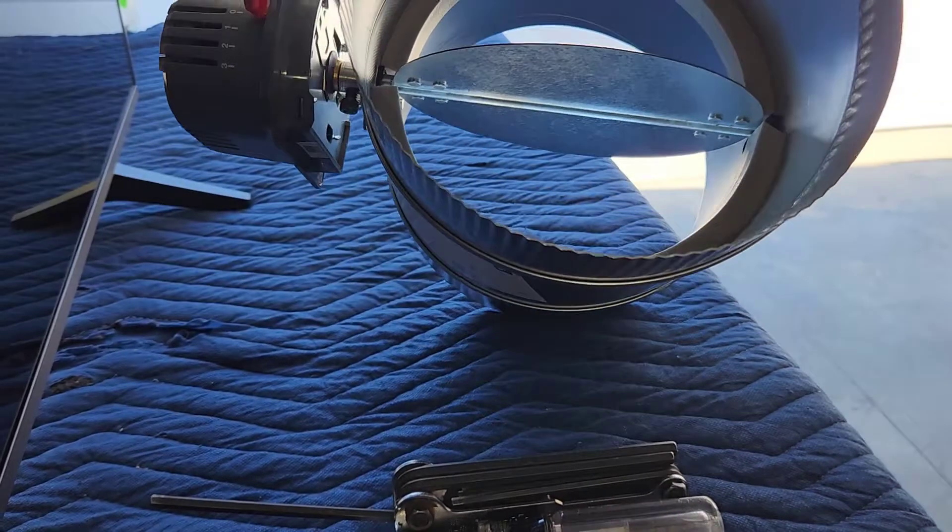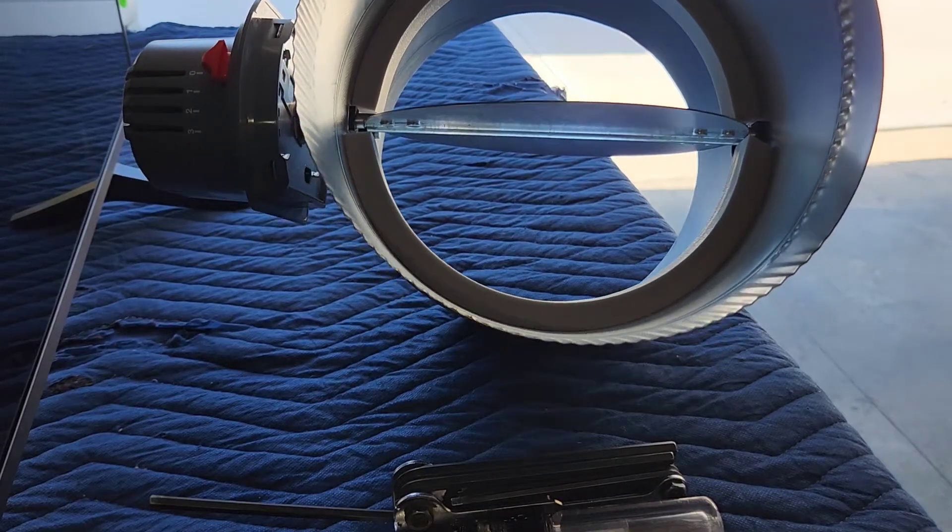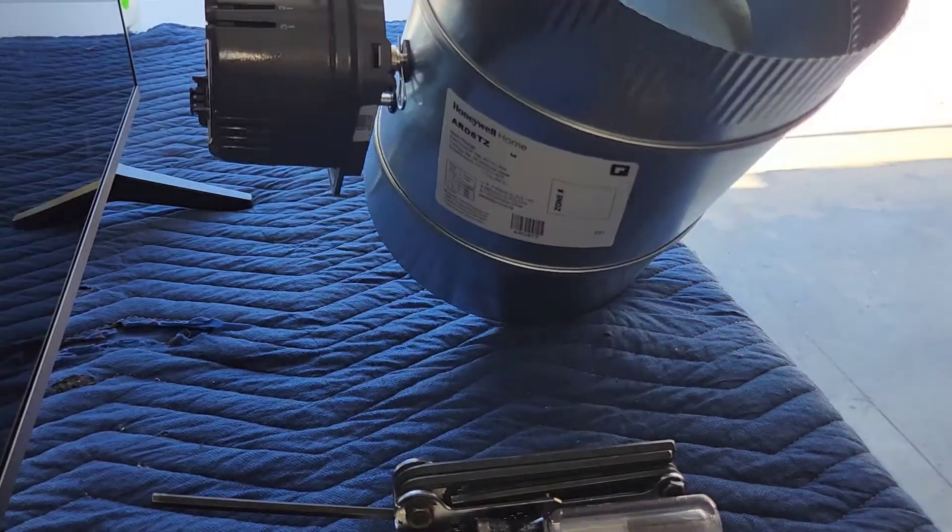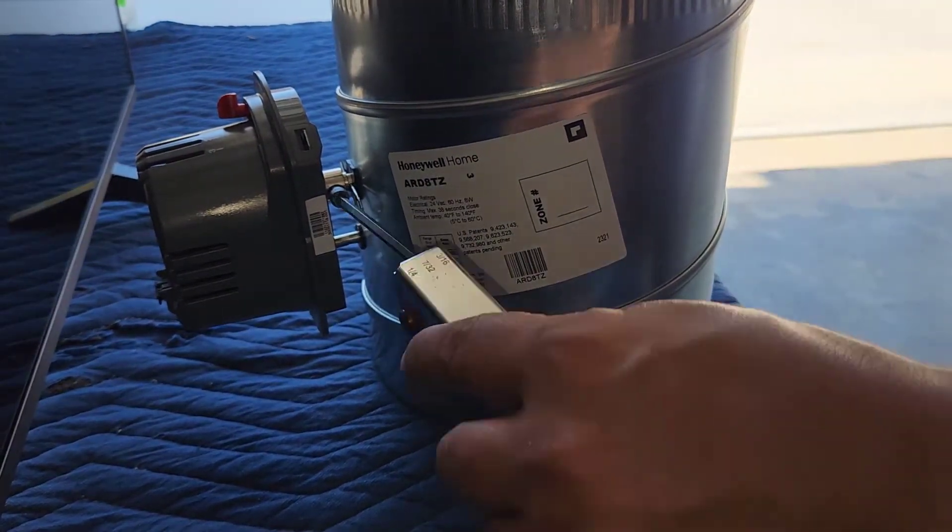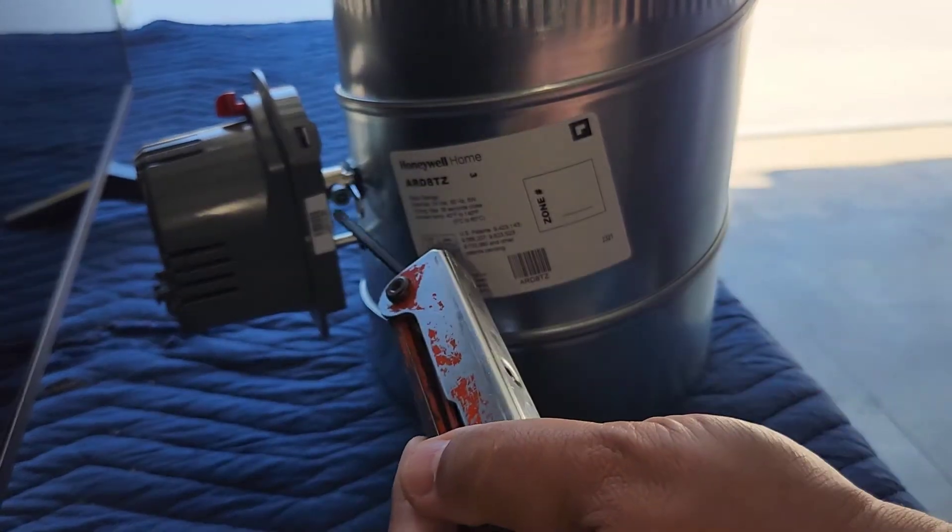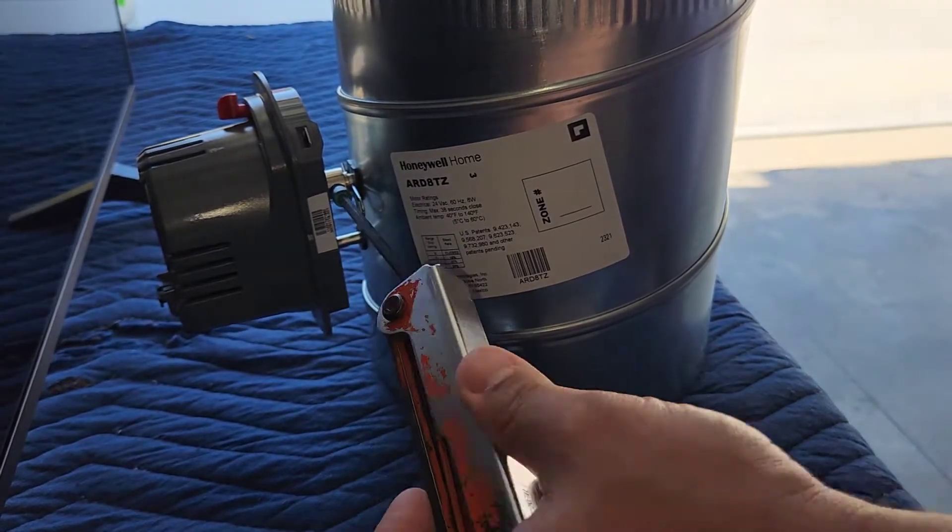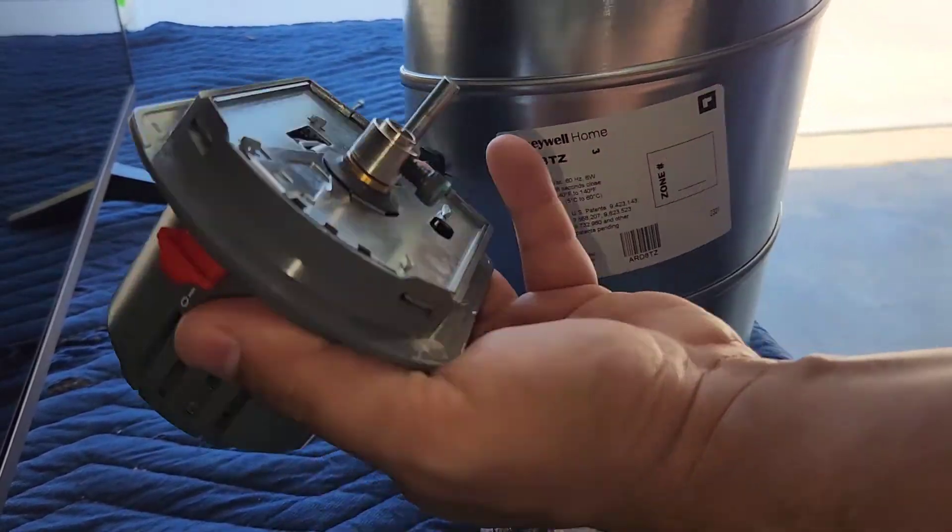So the goal here is to make this damper normally closed where it powers it open. So here's what we're going to do. First thing we've got to do is loosen this set screw. So take your Allen wrench and you don't need to take it off. You just need to loosen it enough where the actuator is not bound to the shaft anymore. And this whole thing will slide off.